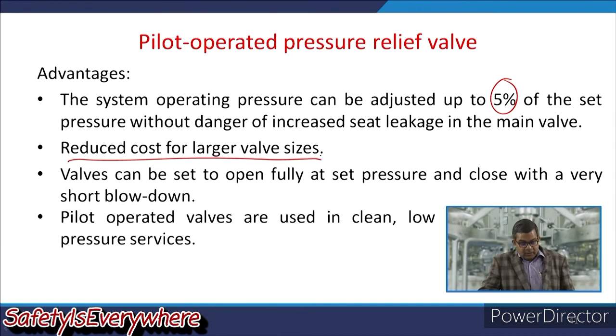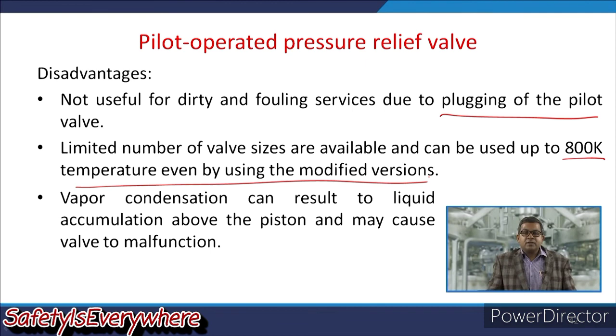While we have several advantages, there are also several disadvantages for these pilot operated pressure relief valves. They are not useful for dirty or fouling services due to plugging of the pilot valve. A limited number of valve sizes are available, and they can be used up to 800 Kelvin temperature, even when using modified versions. Vapor condensation can result in liquid accumulation above the piston, and that may cause the valve to malfunction. So these are the several disadvantages of these valves.